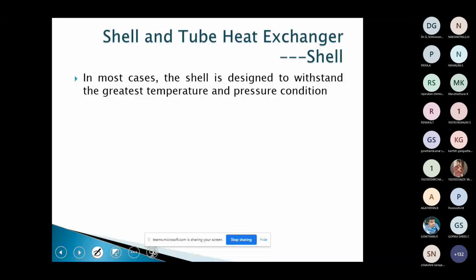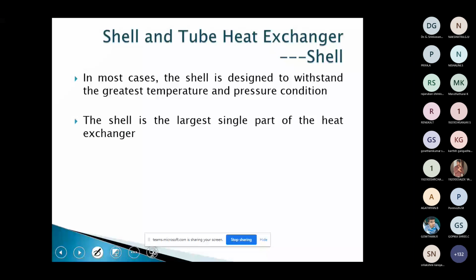Right. Coming to the most important component of your shell and tube heat exchanger: the shell and tube. First, the shell. This must be designed to withstand the process conditions, mostly pressure and temperature. I think we have seen the temperature, maybe we can go up to 600 degrees. So if you want to carry out high pressure and high temperature operation, then we have to select the materials of construction based on this temperature and pressure. These are the foremost things. And then the properties of the fluid, whether it is corrosive in nature or not. So these things should be considered for the selection of materials during the design of shells.